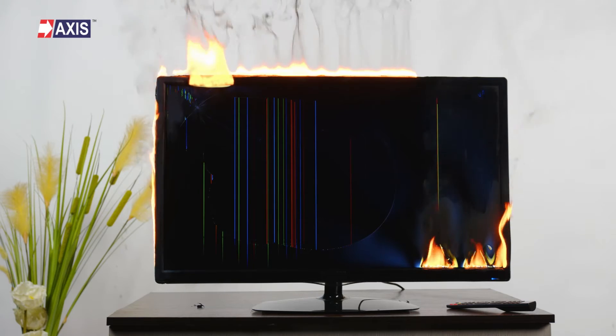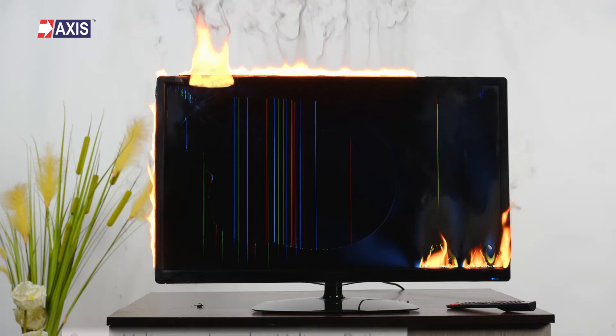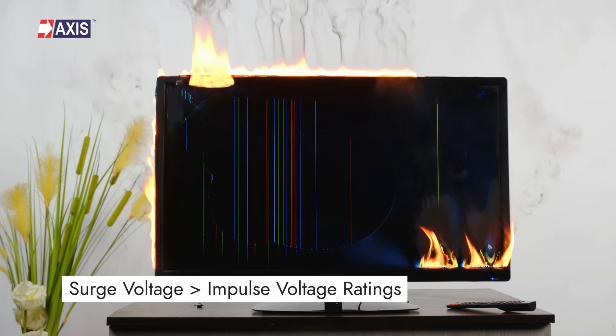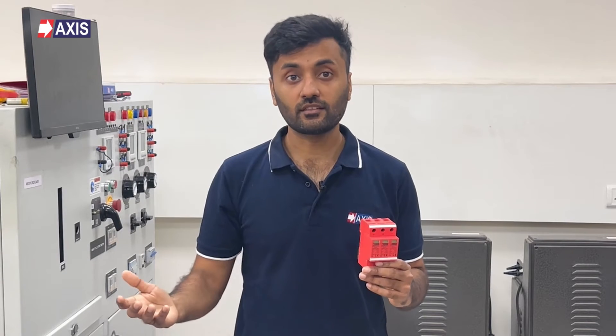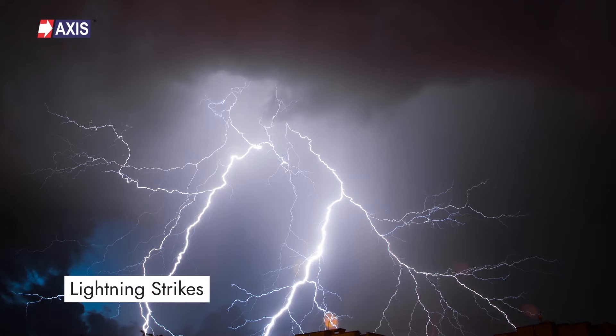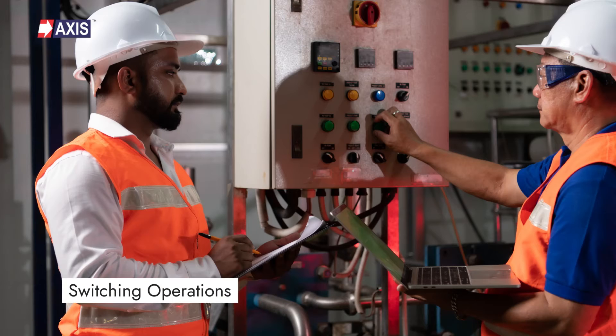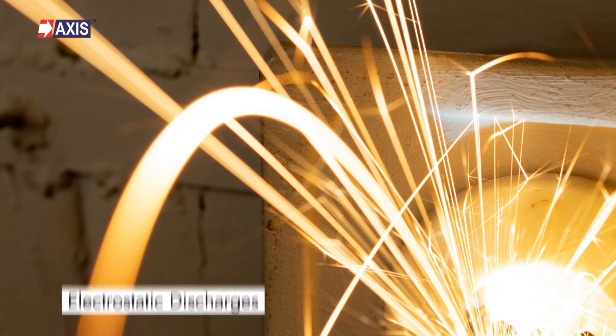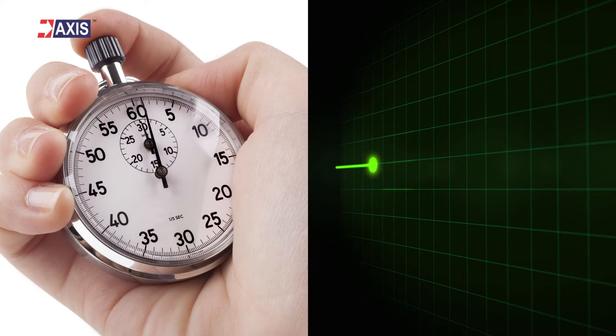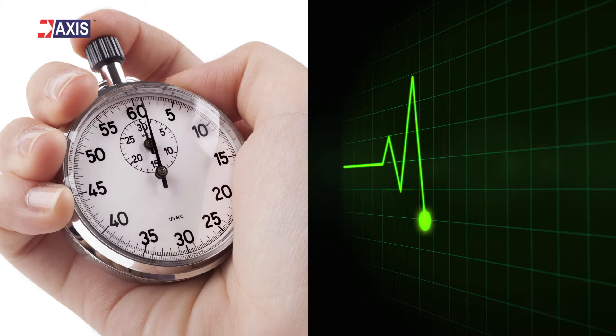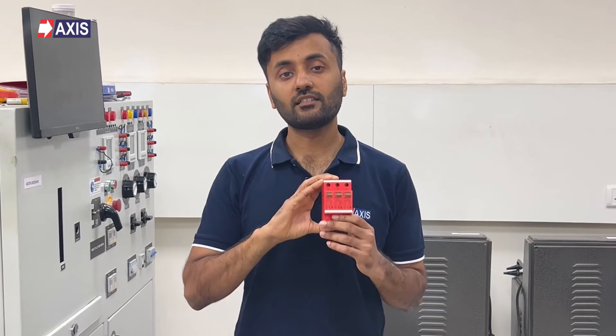Electrical devices can malfunction or get damaged if a surge voltage goes beyond their impulse voltage rating. Surge voltages, often reaching high kilovolts, are transient — they occur in a very short time but with high energy, which can damage your equipment. These are caused by lightning strikes, switching operations, and electrostatic discharges. Since these surges last from a few microseconds to several hundred microseconds, their short duration and high amplitude can cause sudden voltage spikes.